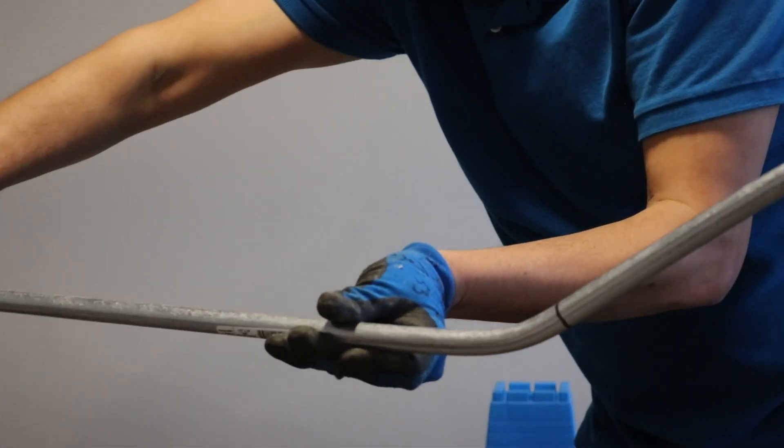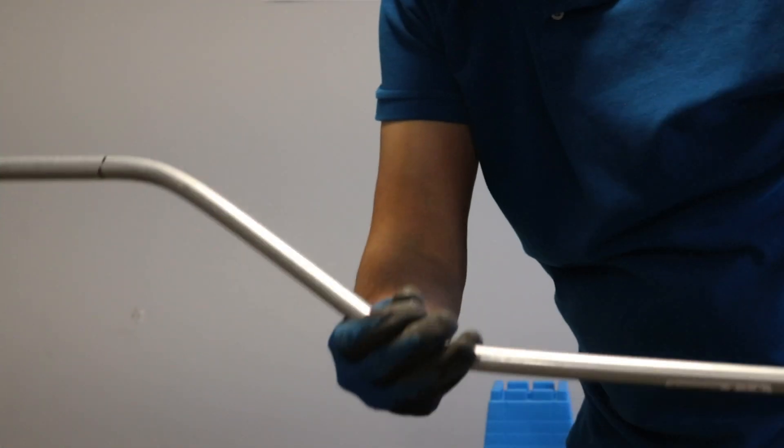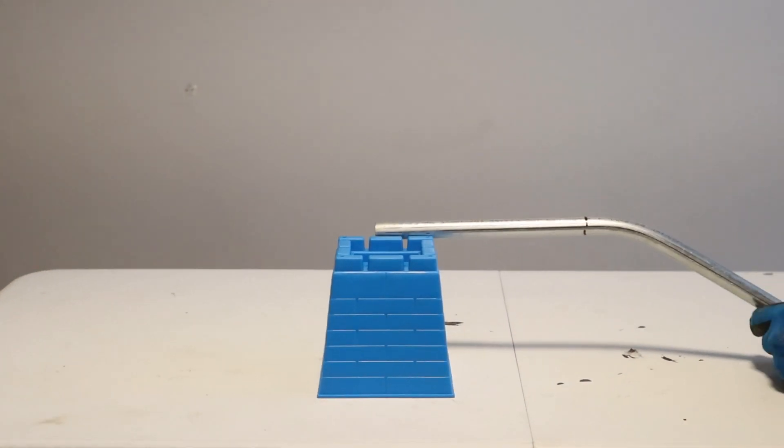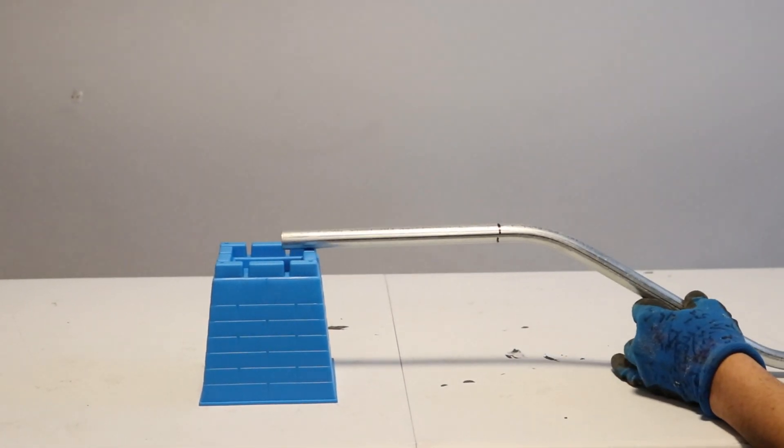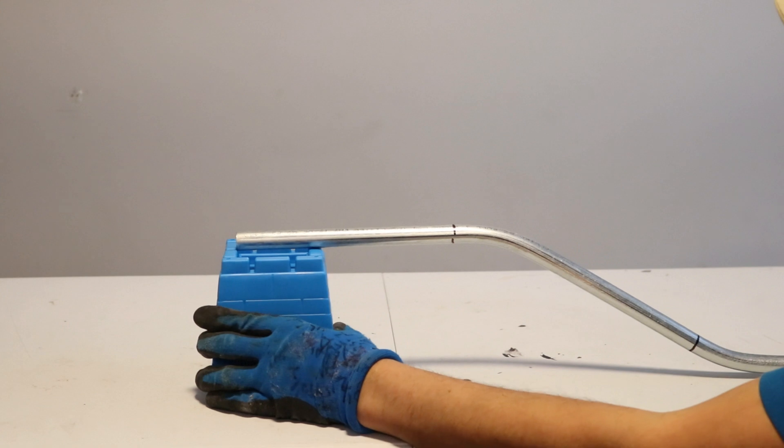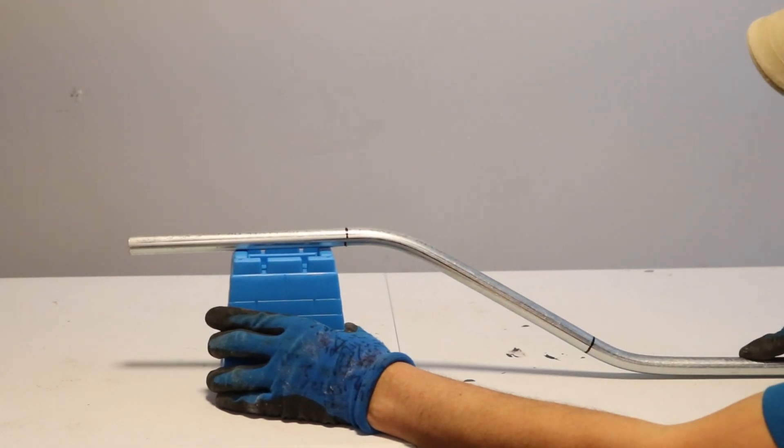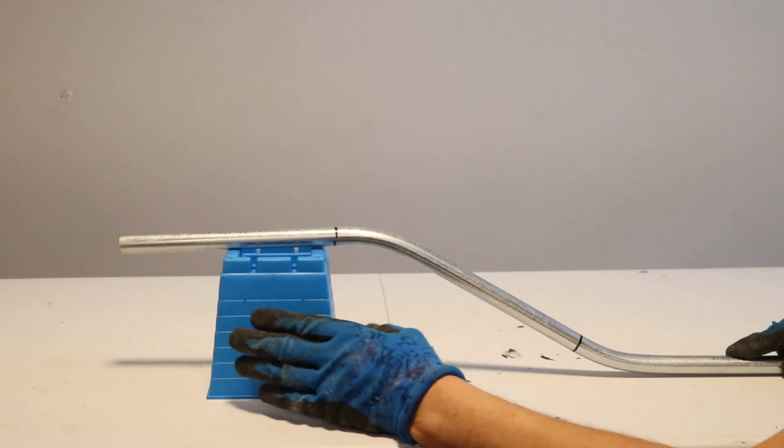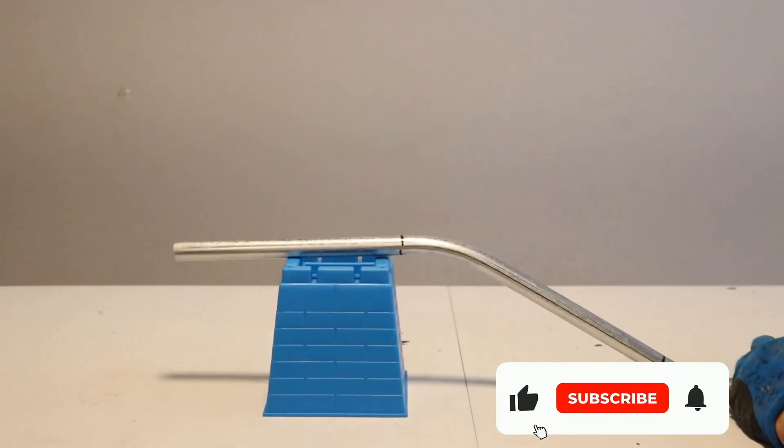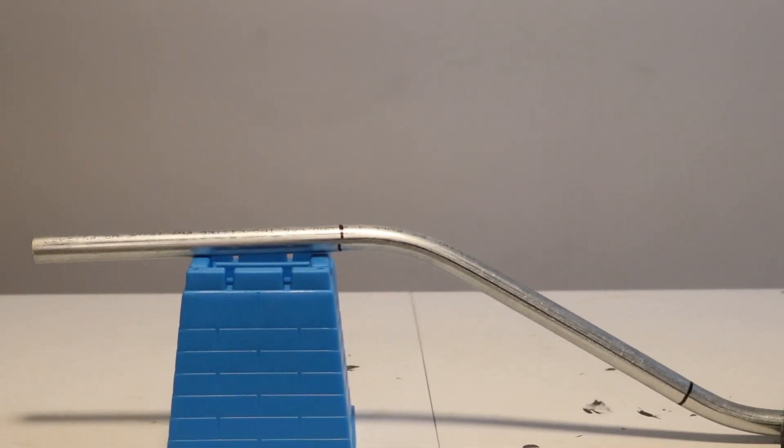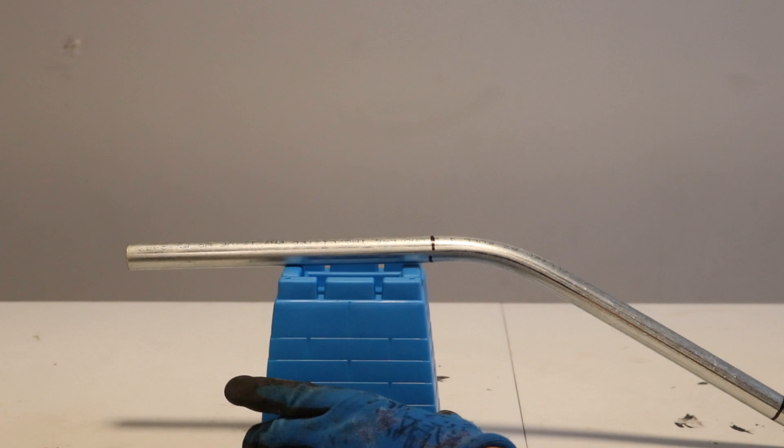That's my 30-degree bend, alright. So my 30-degree bend is done and we're gonna check it. Looks alright. So here you go. My 30-degree bend on a five-inch obstacle is a perfect bend. You can see it's a perfect bend. This is very good and clean bend, and that's my 30-degree bend.